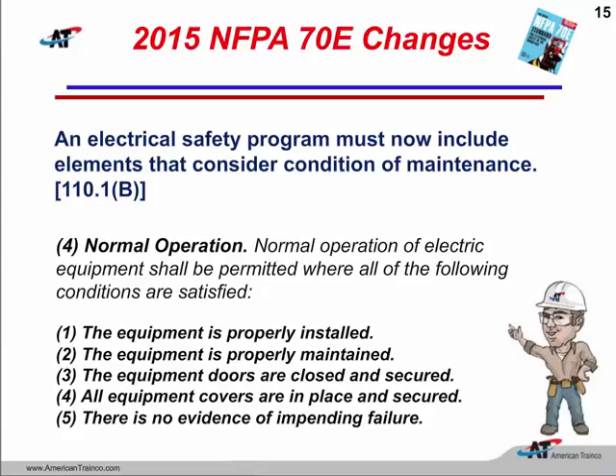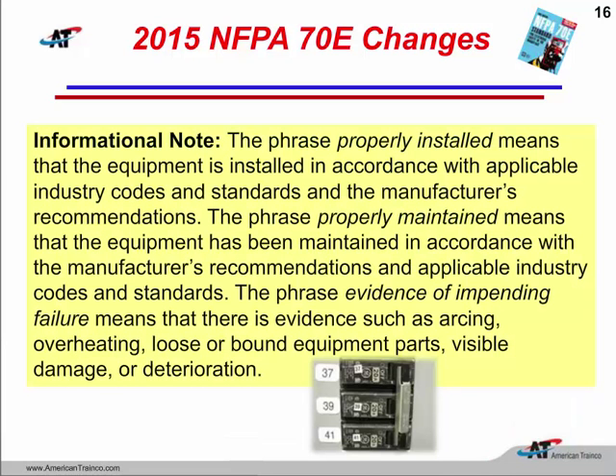And if we can satisfy these 5 points, then really there's no PPE that we have to put on to operate the equipment, because there are no exposed conductors, there's no exposed energized parts, really no evidence that there is going to be an arc flash, arc blast. So if that is the case, we can operate the equipment normally, but otherwise we're going to have to put some personal protective equipment on to just operate the equipment, to turn something on and off.